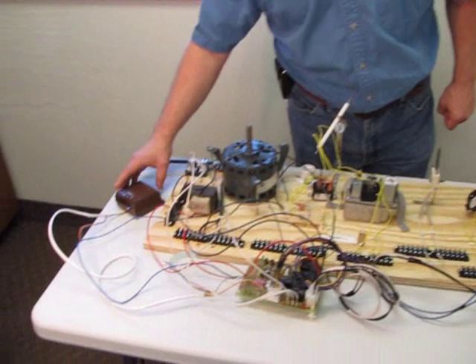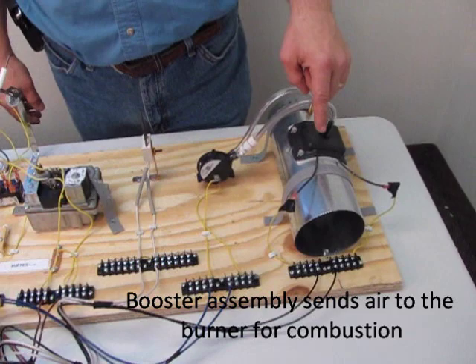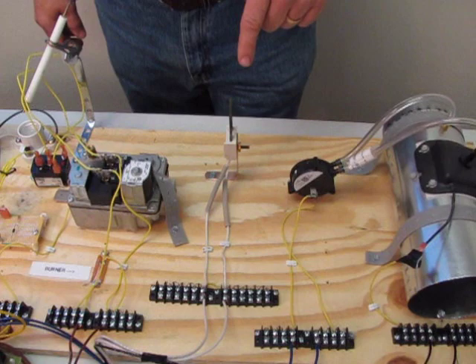So let's turn on the thermostat, make it call for heat. The first to come on is the booster assembly, and what it does is it sends air to the burner. When it's on, it trips this pressure switch.